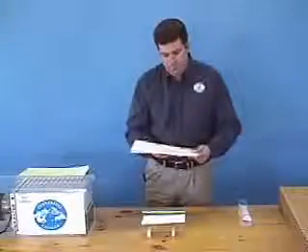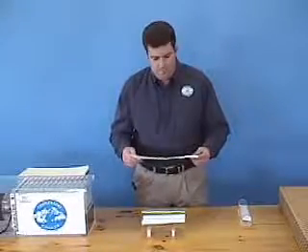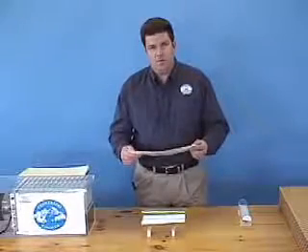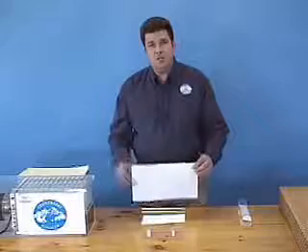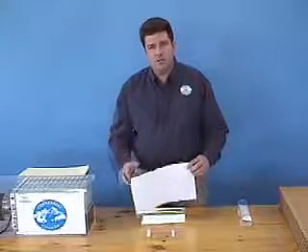The plastic is the heat exchanger, and it in turn will cool and pull heat away from the air on the other side. This is similar to how your body, skin, and perspiration work together to cool your body. Indirect evaporative cooling is called sensible cooling, and heat energy is removed from the product airstream.